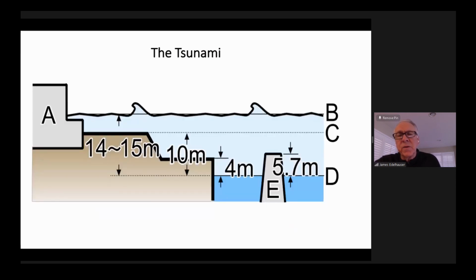This gives you an idea of the wave. It shows normal sea level. They had a seawall that was 5.7 meters, close to 20 feet above sea level. The normal grade at the plant, the lower grade, was 4 meters. Where the plant actually was, the normal grade level was 10 meters, or 30 feet above sea level. You can see the wave was basically as much as 20 feet or more above the normal grade level, and it flooded out and destroyed their electrical supplies.